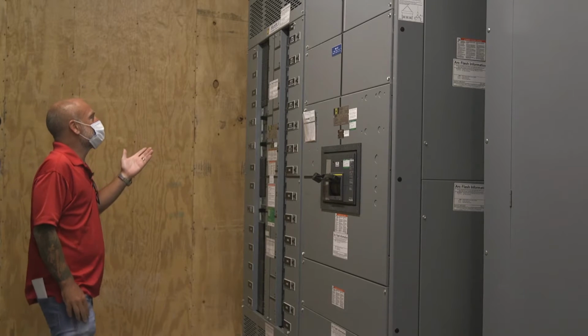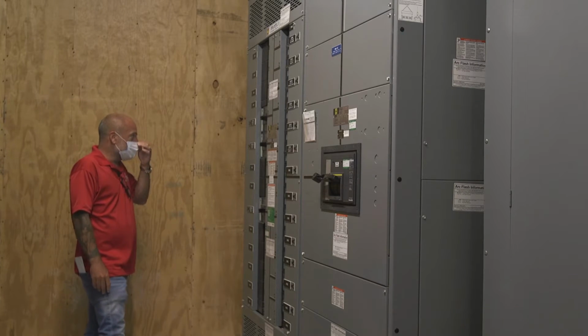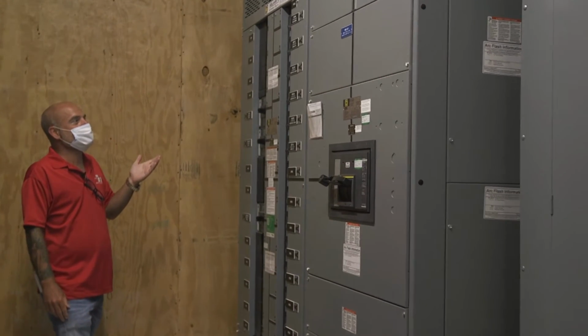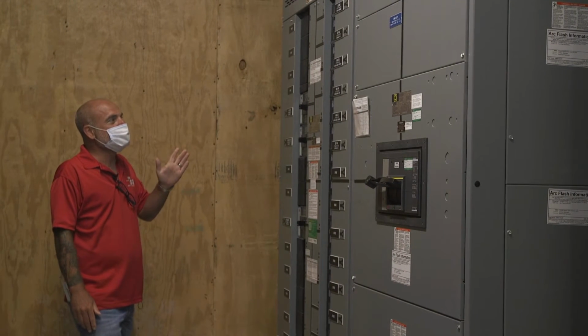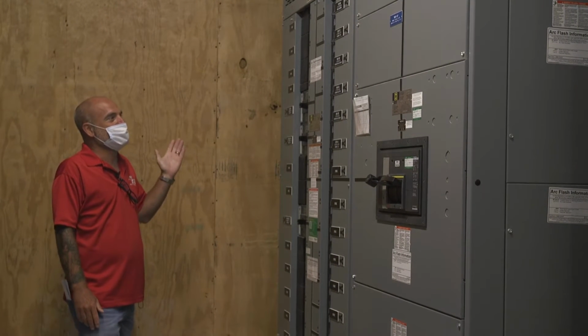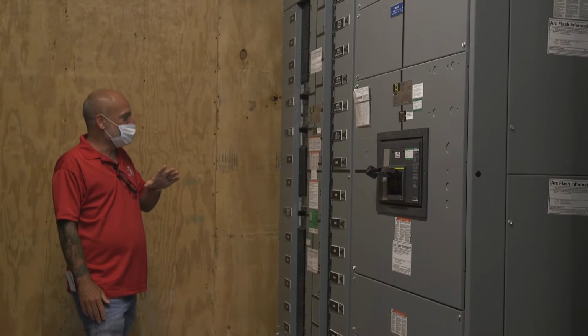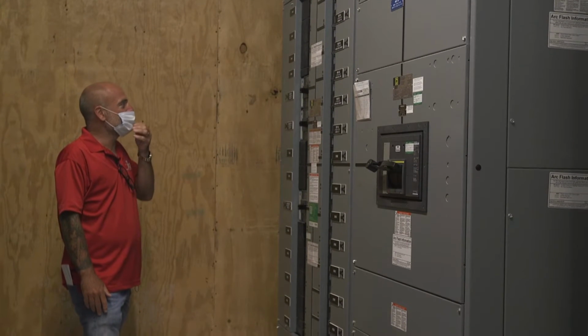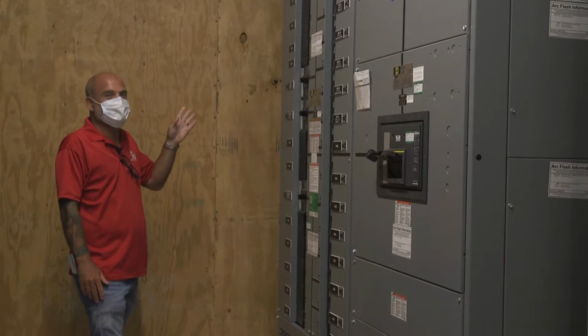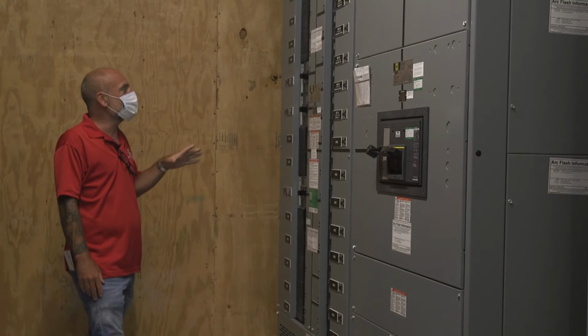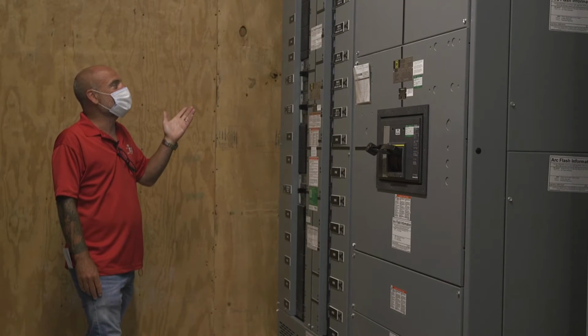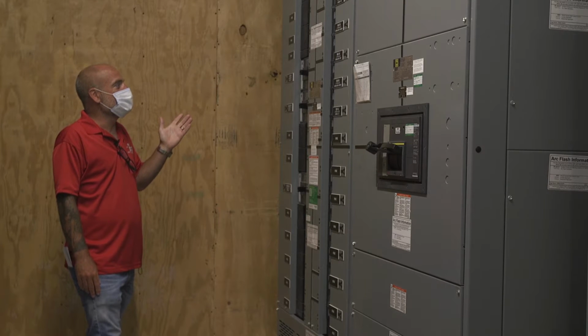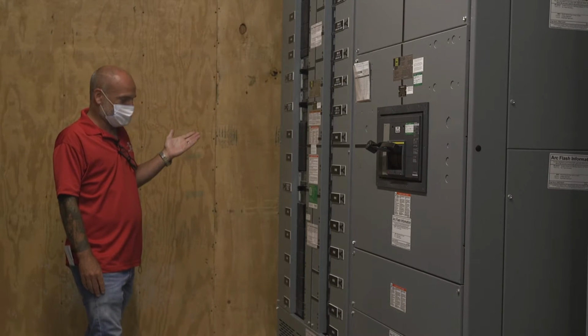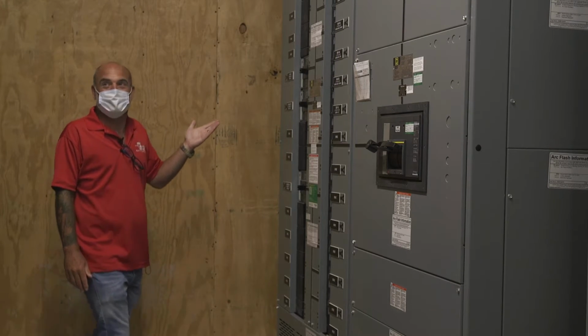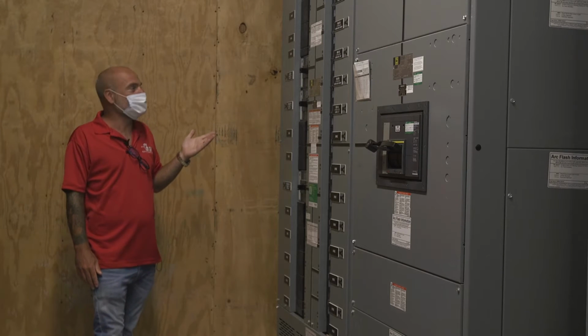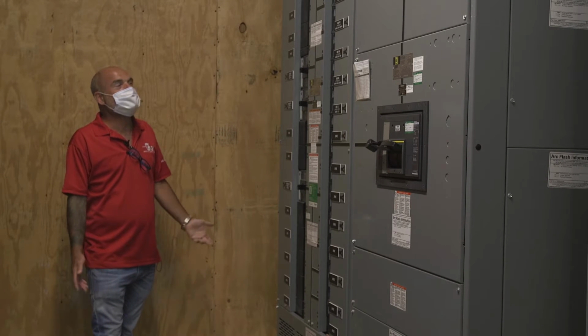Moving into the smaller breakers, pretty much basic same scenario. Trip is in the middle. If you want to disconnect the power, you have to turn it all the way to the right. Some of the breakers in this panel have trip settings, which have been set to the coordination study, so I don't think you guys would have to adjust those. So basically, that's really all you need to know about turning on and off breakers and the trip functions.